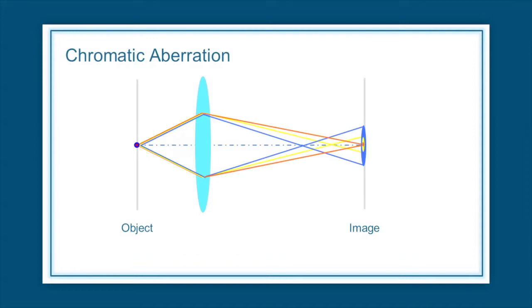These electrons may have different energies for two reasons. One reason is that the electron gun — the source of electrons — has a spread in the energies and wavelengths of the electrons it produces. The second reason is that as electrons travel through matter, they lose different amounts of energy. Each of these aberrations of the electron microscope results in blurring of images and loss of spatial resolution.